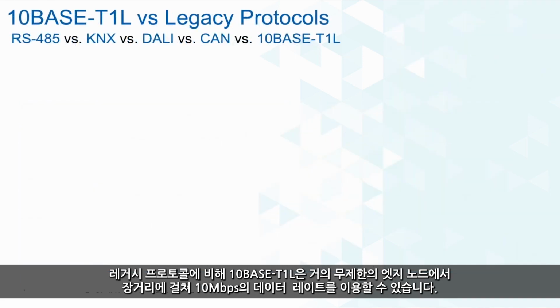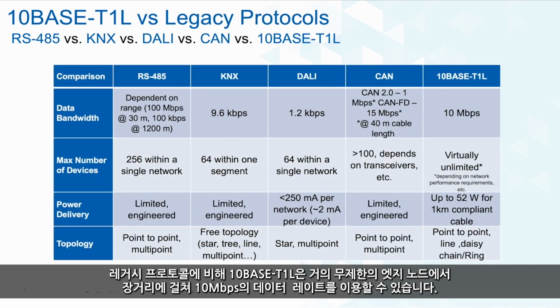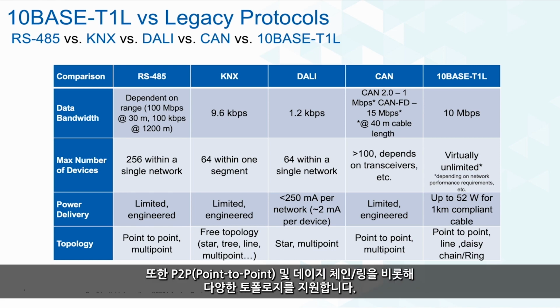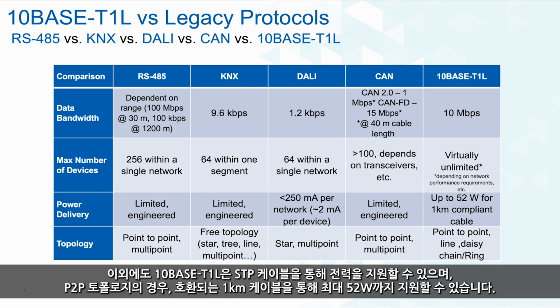Compared to legacy protocols, 10BASE-T1L uses a 10 megabits per second data rate over long distances with a virtually unlimited number of edge nodes. It also supports different topologies, including point-to-point, daisy chain, and ring. 10BASE-T1L can also support power over a single twisted pair of cable, which can go up to 52 watts for a compliant 1 kilometer cable in a point-to-point topology.